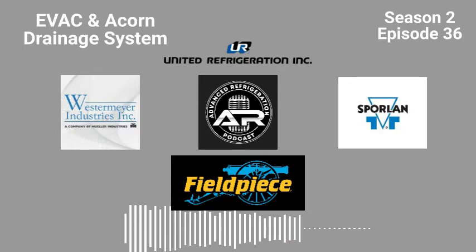That accumulator or buffer box has to be completely empty before you try to calibrate that thing. The reason is that if you have it set at 50% water in that accumulator, then you plug it into the control, now it thinks 50% is zero. So now it's trying to overfill that buffer box with a whole bunch of water in order to achieve that water column to activate the control, which activates the accumulator. So make sure that when you are working on them and trying to calibrate them, you fully empty that box out and also clean any debris that might be in there that might be giving it a false reading.